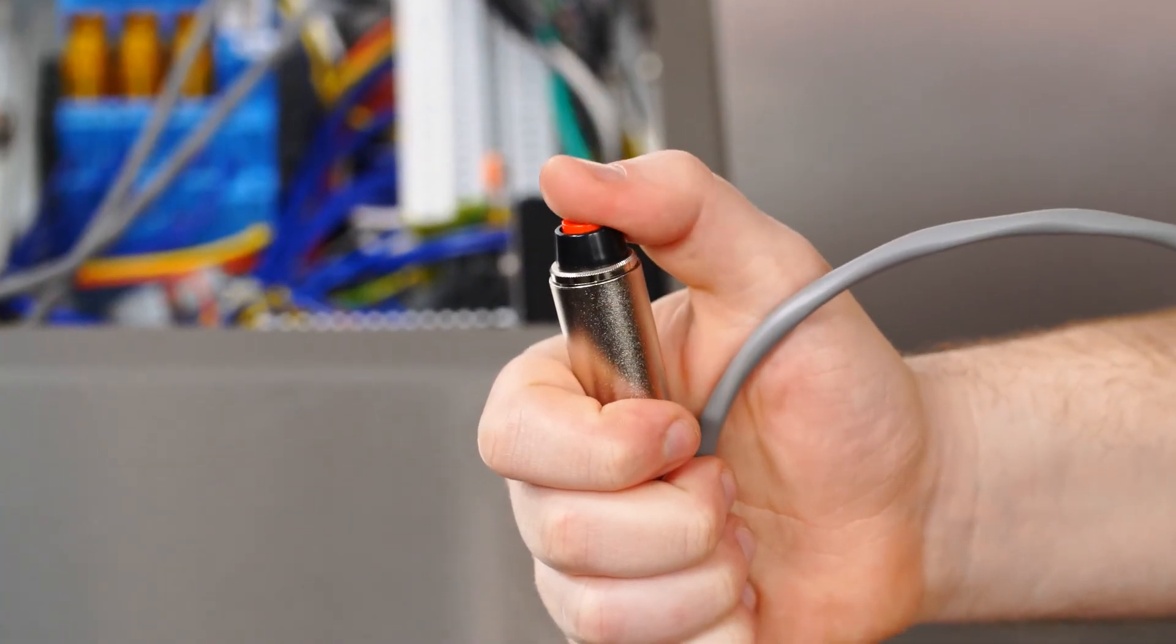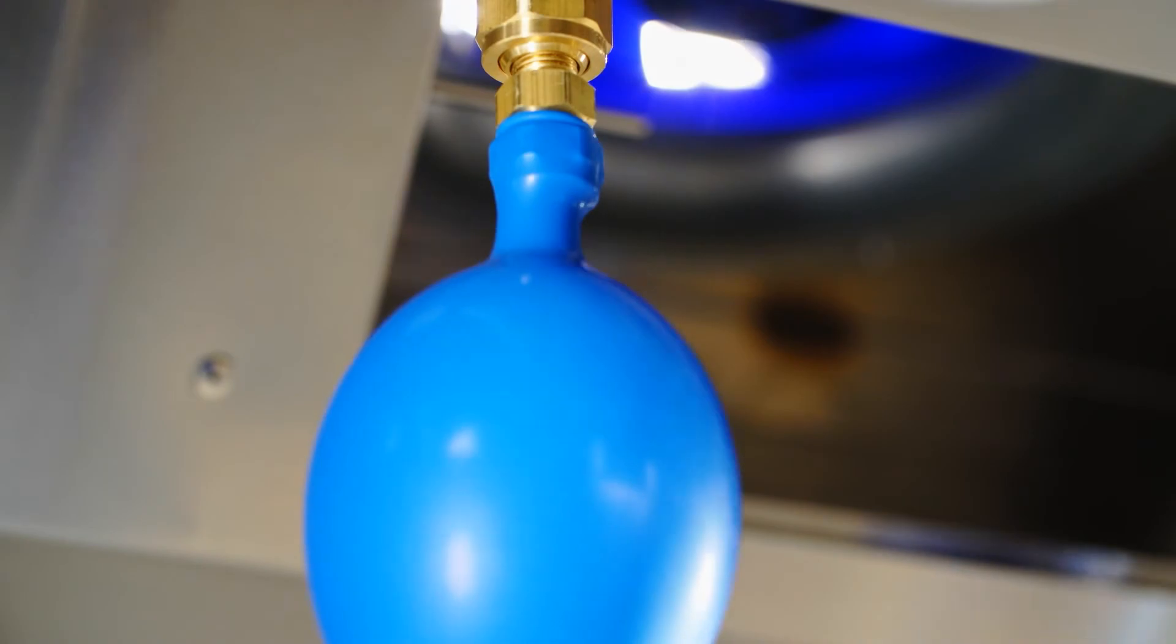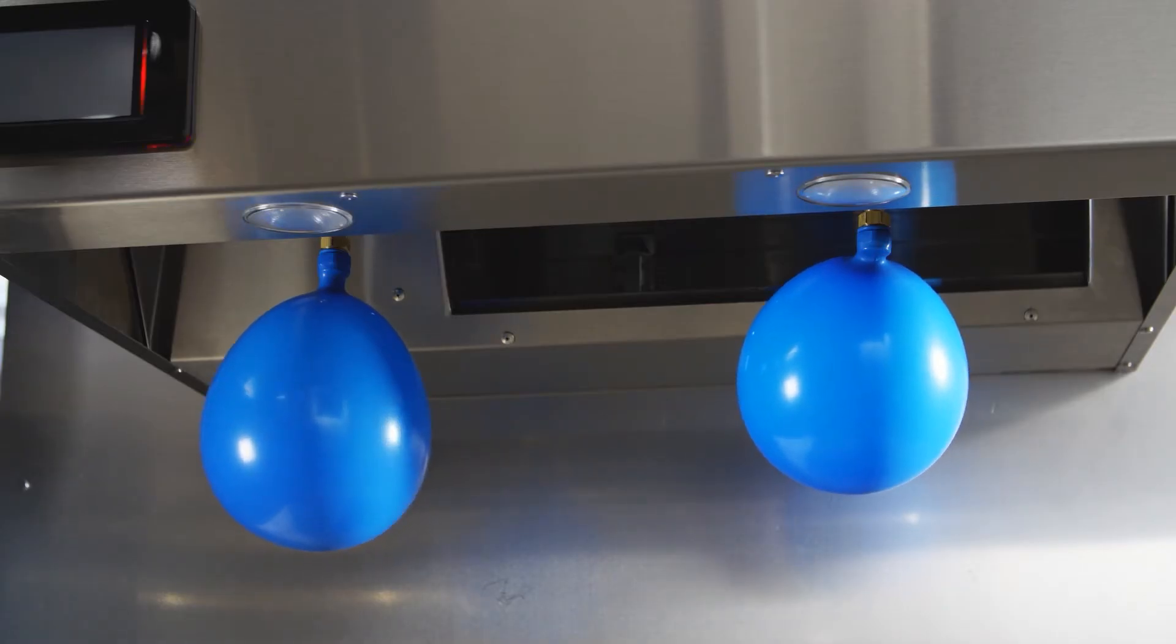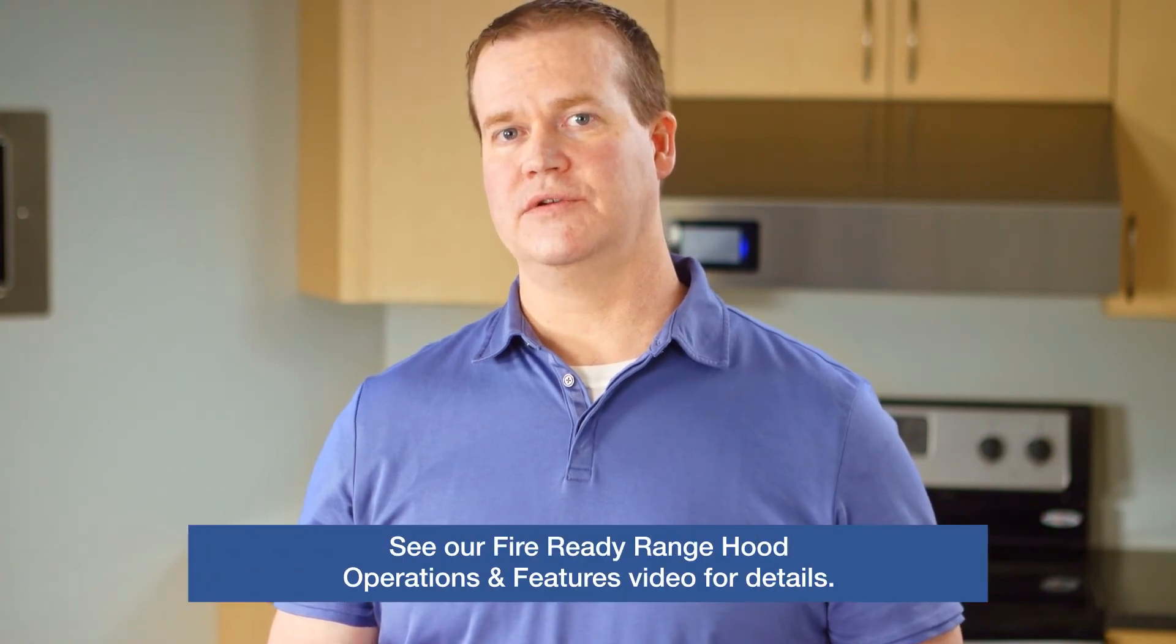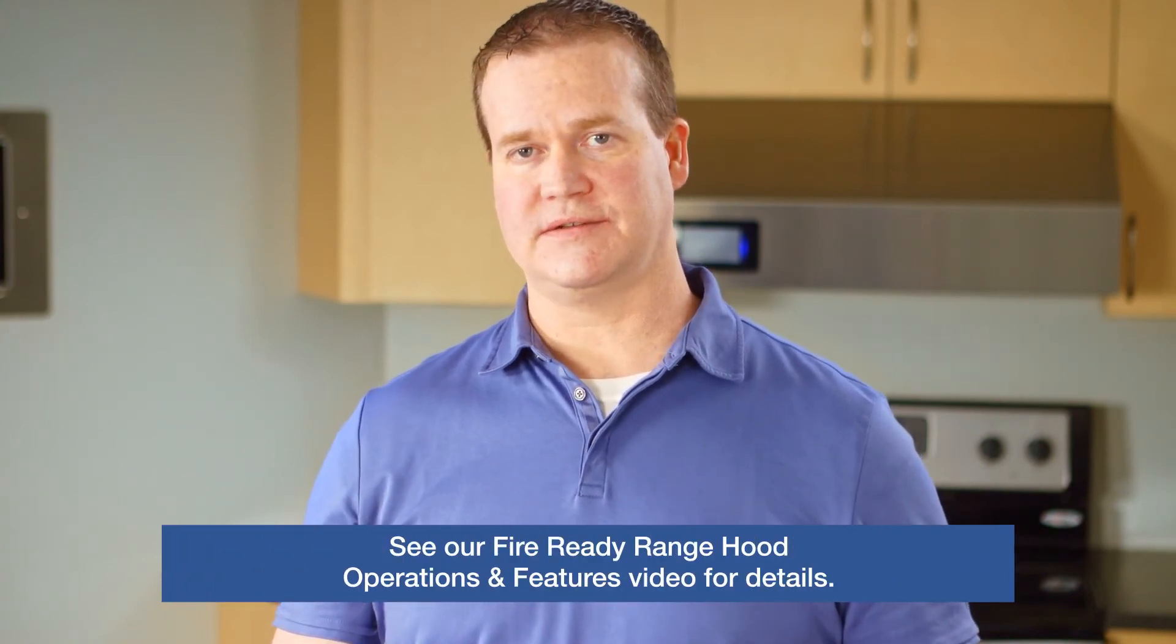Press the red button on the test tool or pull the pull station lever to simulate a fire. As we just observed, the test tank has depressurized due to the system's activation of the solenoid latch on the tank. The disconnect has also shut down the electric or gas range disconnect. Additionally, if the system is tied to a building alarm panel, a signal is sent to trigger its activation. Please see our video on hood operation for further details on this.